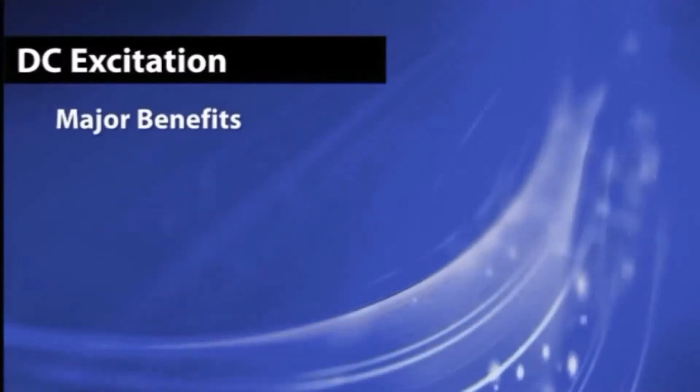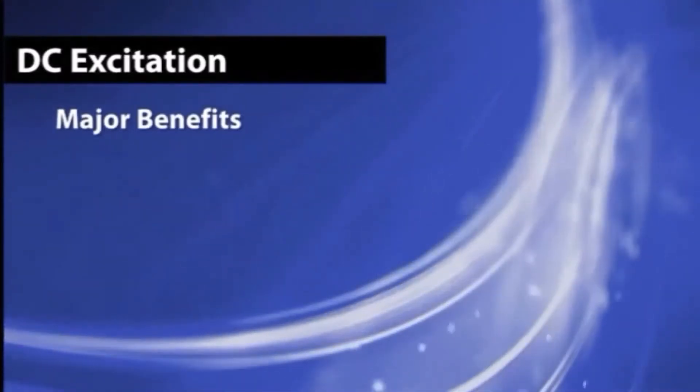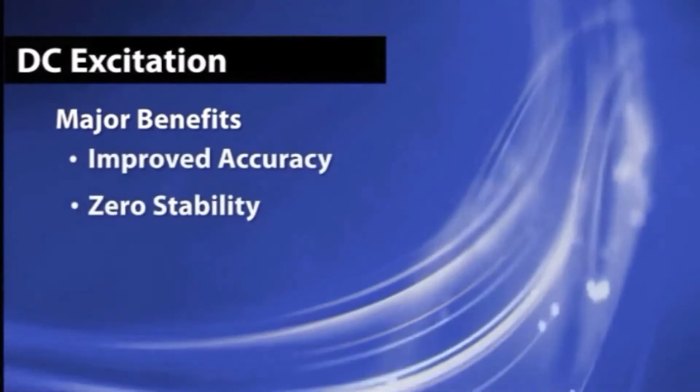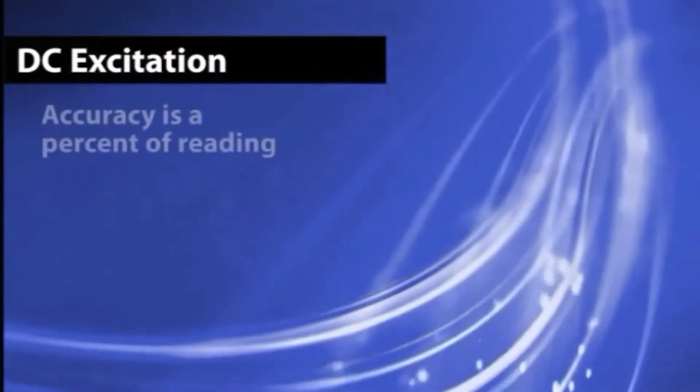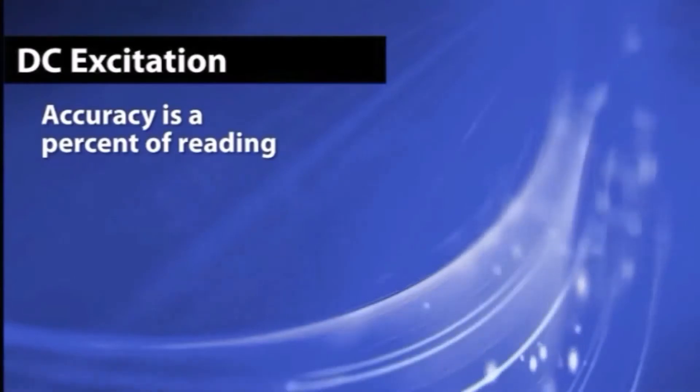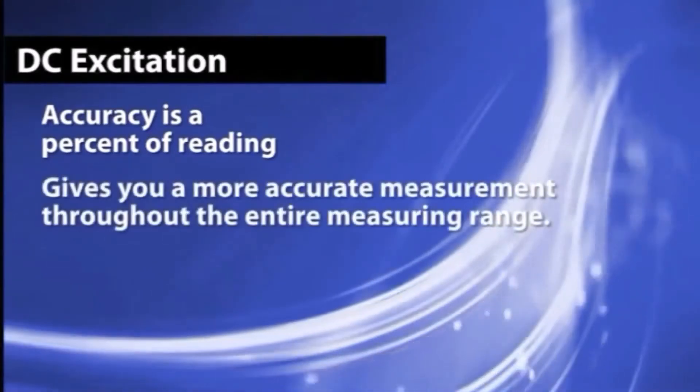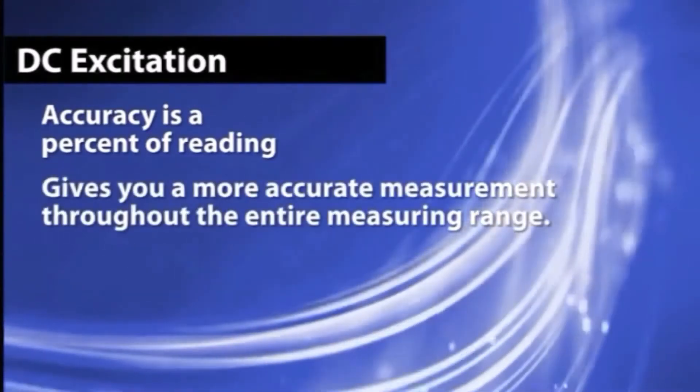The major benefits of pulsed DC excitation over AC excitation is the improved accuracy and zero stability. The accuracy of a DC type meter is a percent of reading. This gives you a more accurate measurement throughout the entire measuring range.